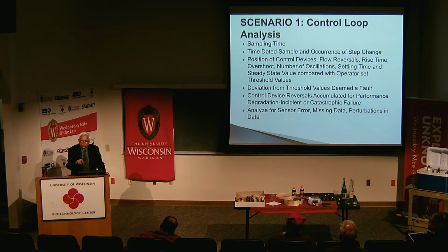So you got a step change. And then you have to see what the control loop performance is. How quickly does it start rising? Are there oscillations in it? How much time does it take to come to steady state value? So these are all the things that you have to consider. Now, in this case, because you can't analyze fault detection when the control loop is in action, because it has to maintain control, you can't go and stop things and analyze for faults. So all the data during the control loop analysis is sent to the cloud by the smart building facility management system. And during off-peak, you analyze it and see what to do about it.